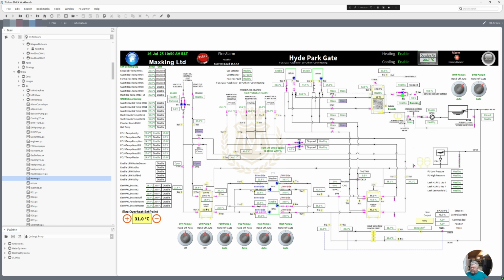The problem we have with this particular system is we wasn't allowed to place any units outside on the roof or on the walls. So the LTHW that we are producing here, the 38.9 degrees coming back 33.9, is going through this CV9 and going to this plate heat exchanger and then coming back. So we're using the plate heat exchanger this side to dissipate the temperature, the LTHW, which is the byproduct of when we're cooling. The LTHW is the byproduct, so we've got to get rid of it somehow.